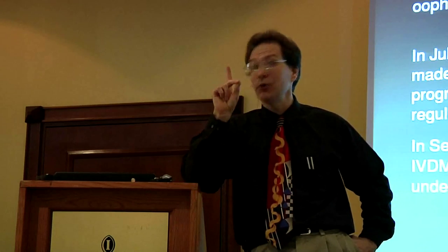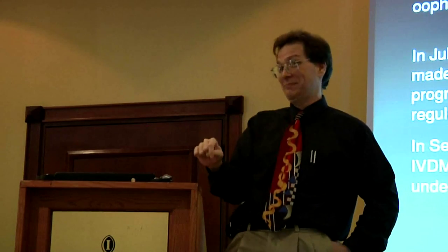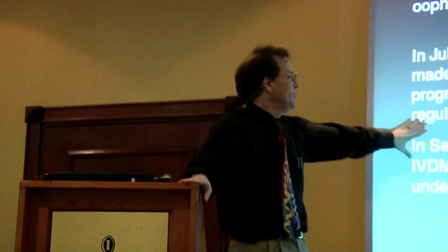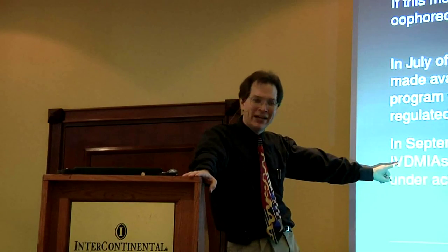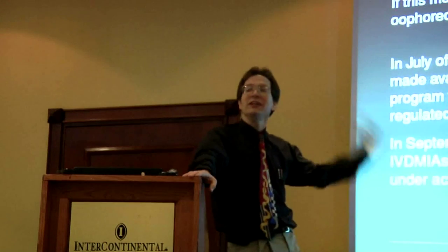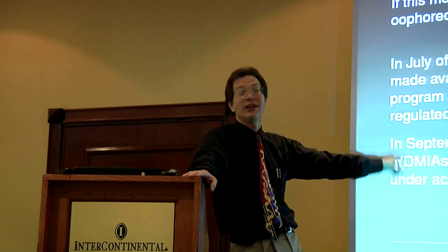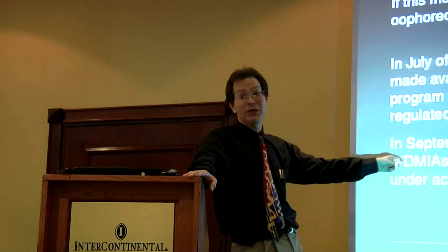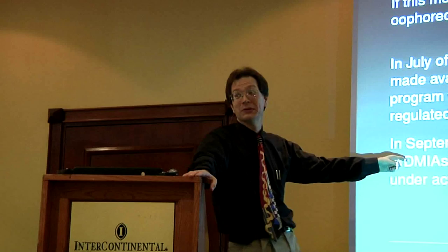And this ruling is important because it means it is subject to the regulations governing devices. This then was appealed and went on for 2 years, in the course of which the FDA started issuing new guidance to govern IVD MIAs, in vitro diagnostic multivariate index assays. Basically, microarrays, proteomics, anything that involves thousands of measurements, this is where they're saying these are the hoops you need to jump through to get us to approve it. This one is still being negotiated with industry because industry is still not sure that they fully understand what the FDA wants.